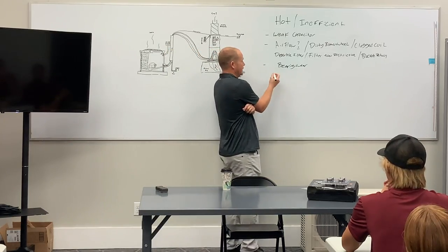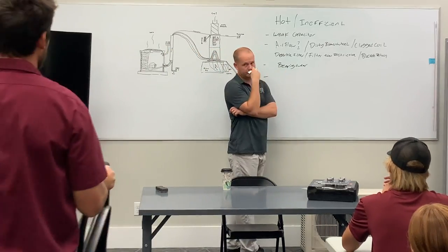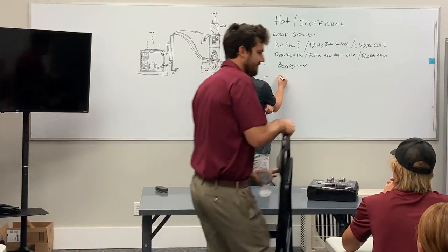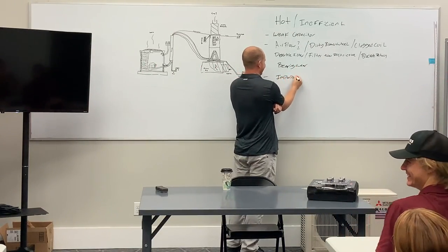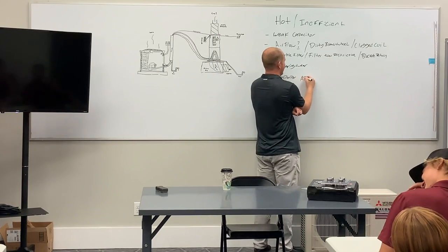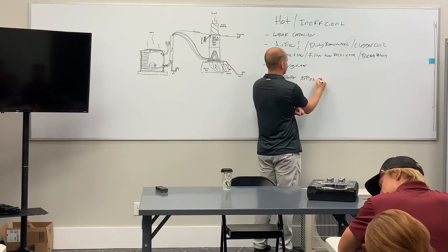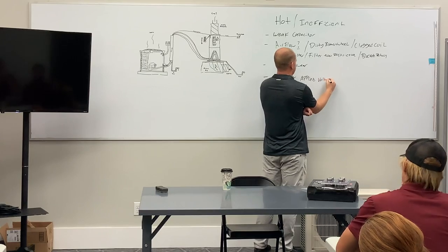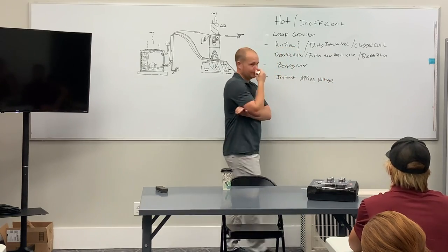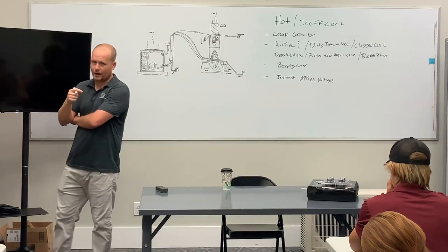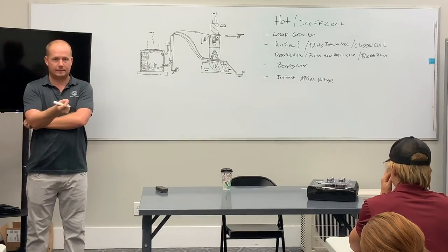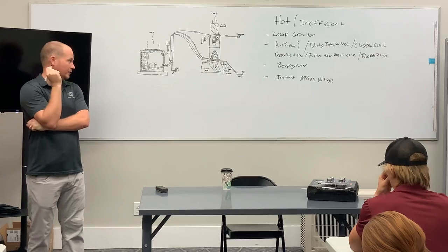What else can cause a hot, inefficient motor? Improper applied voltage. Meaning that anything that would cause the voltage to be either too low or too high for the motor's design can result in a hot or inefficient motor.